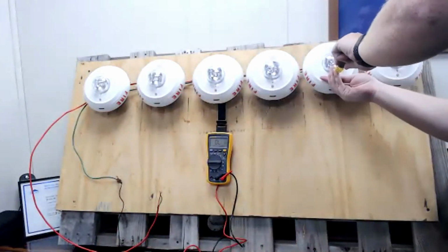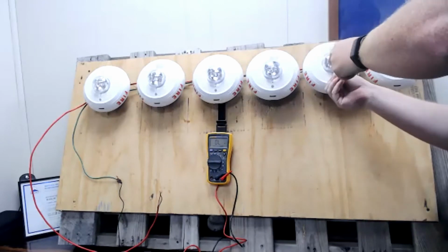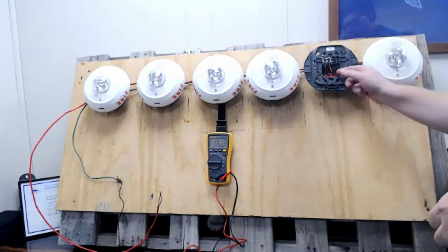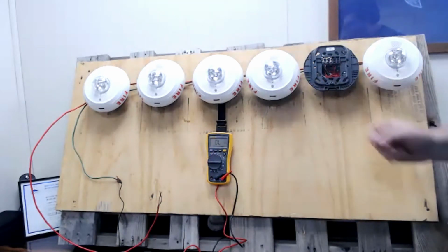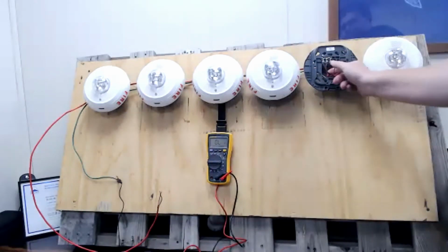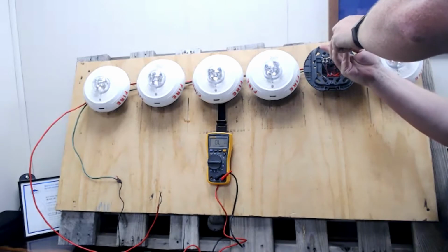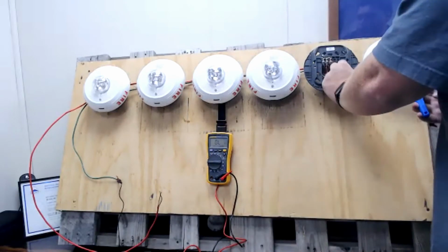All right. Now I'm going to come over here. I'll try to stay out of the way. And like I said, we're going to come to this because this one's the center of the second half of the circuit. I'm going to open this device up, and I've already found my open circuit right here. I can see where the copper was put under it, but maybe the wire was nicked when it was being landed. And I can pull, the other ones seem to be doing just fine. So what I'm going to do, I'm going to go ahead and break it. I'm going to get rid of that conductor right there out of my way. Pull this over here. And I'm going to restrip this wire.